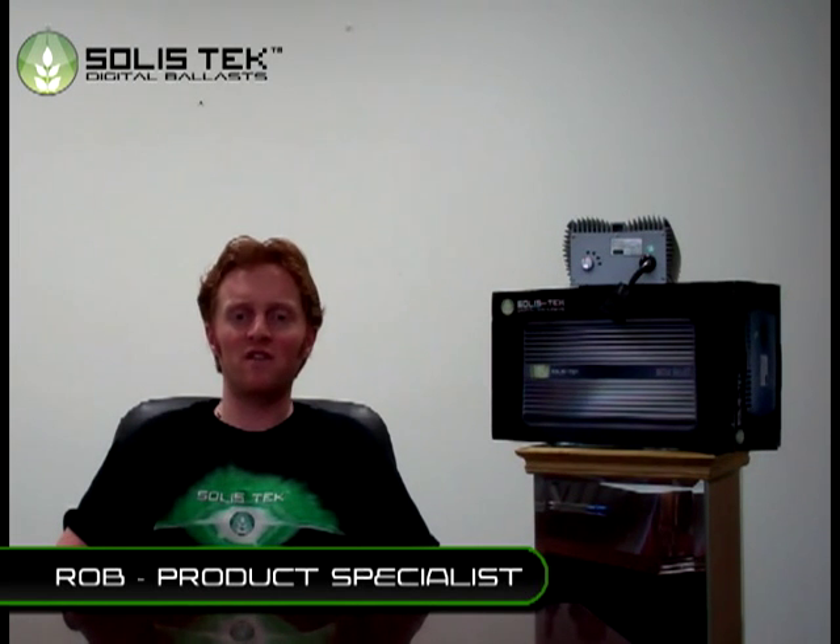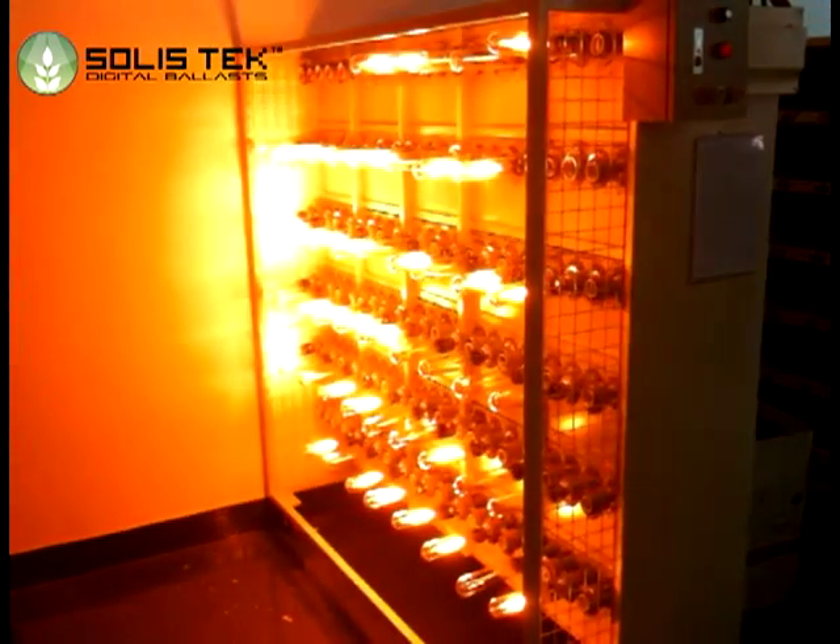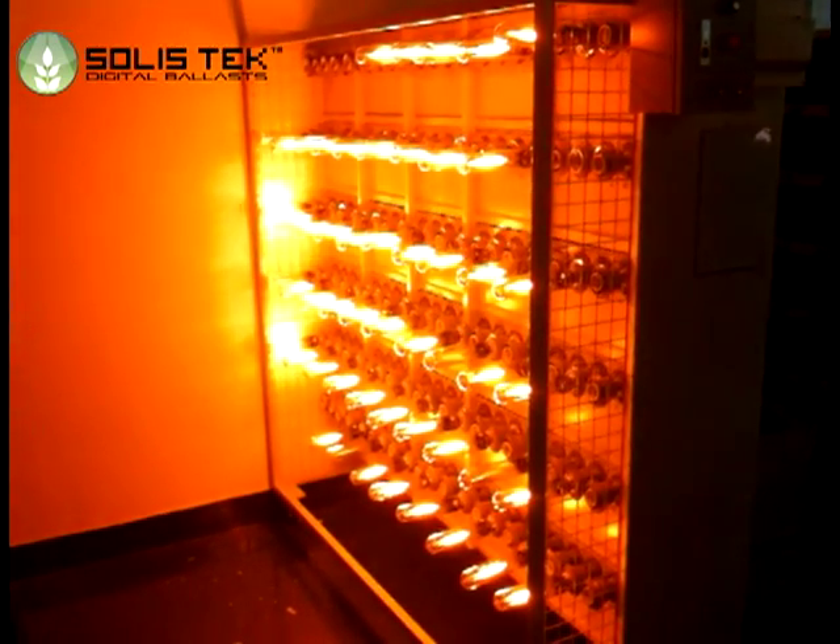Our primary and revolutionary safety feature is ignition control. Whether you are powering up 10 units or 100 units of Solis Tek Digital Ballast, the electrical draw is completely balanced by our internal software. Our software will ignite lamps one at a time, which will prevent electrical surges and spikes and protect breakers from overloading.